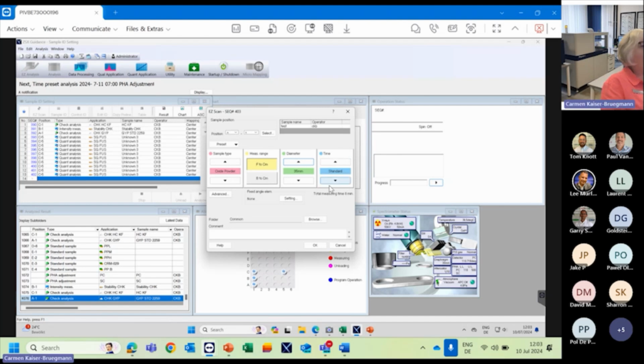We can also define the measurement time. So we have standard short measurement time, which is 2 minutes. Standard is 8 minutes, so it's a longer spectral scan. And then a long method, which is 17 minutes. So this will be for the measurement from fluorine to curium. So remember, semi-quantitative has a higher measurement uncertainty, and we just would like to identify certain elements within the material. So this is why, if you would like to do a very short scan, we could, for example, just go for 2 minutes and just identify the peaks.